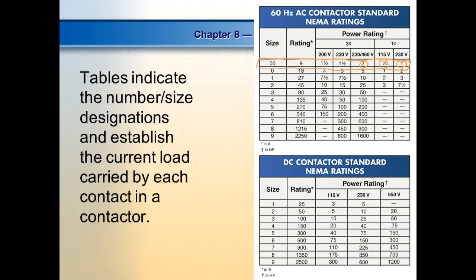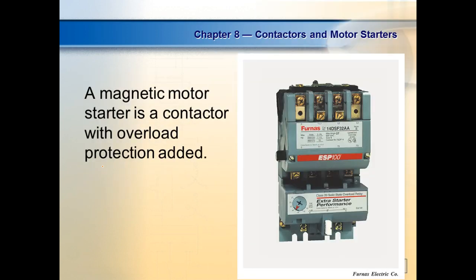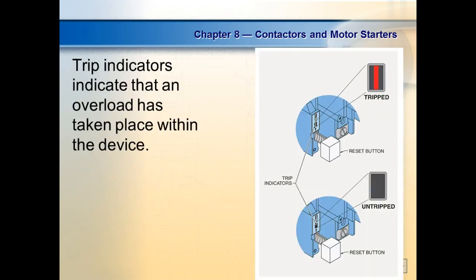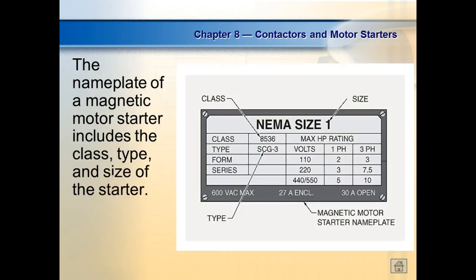So y'all found this. What page is this on? 254. So this one right here is a size 0. I mean a size 1. So what should it be? If you look at the chart, size 1 should be able to handle what? 2 horsepower at 110 volts. It should be able to handle 3 horsepower on 220 volts single phase, and 3 horsepower on 3 phase.